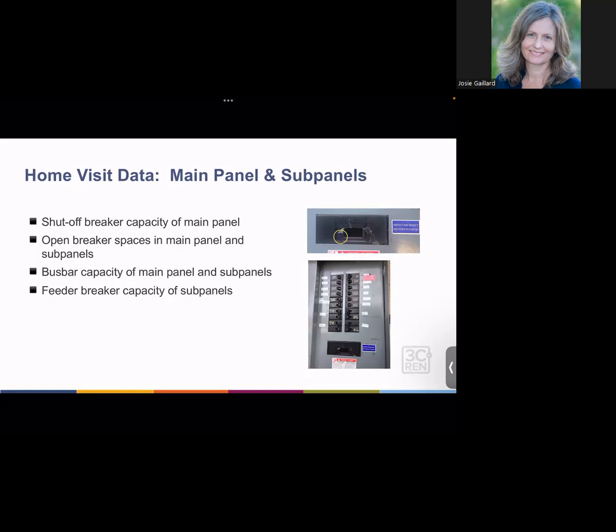Before this point would be the shutoff breaker capacity — are we working with a 100 amp panel, 125 amp panel, or 200 amp panel? What breaker spaces do we have in the main panel and any sub panels in the house? What's the bus bar capacity of those panels, and what is the feeder breaker capacity of the sub panels? The main panel feeds into sub panels, and each circuit feeding a sub panel has a breaker, so it's good to know the max that sub panel can handle.